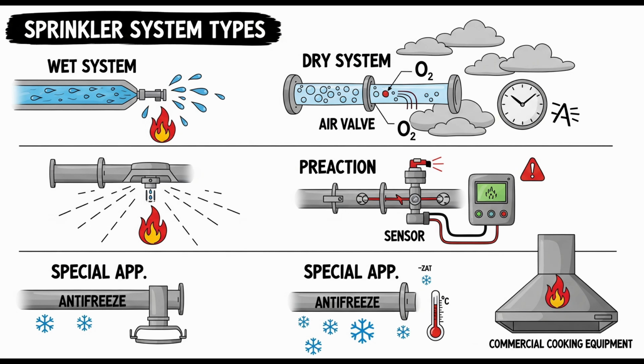Okay. Given our focus on keeping water out of cold areas, that refrigerated space exception is important. Takes longer to refill the pipes, perhaps, or maybe condensation is more of an issue. Possibly. The standard doesn't specify why, but it acknowledges the unique challenge. The goal with the air supply, especially in cold areas, is to minimize moisture entering the system. Right, dry air is key.